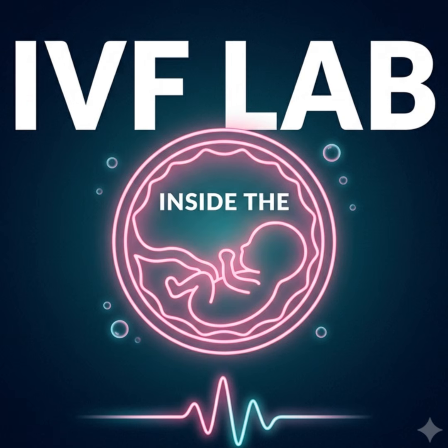Turning that coarse focus knob, absolutely terrified that you're going to drive that heavy metal lens straight down and crush the glass slide. Yes, because the focal length requires the glass to be practically touching the sample. And if you have a massive, bulky metal lens block sitting directly on top of the Petri dish containing your oocyte, the airspace is completely occupied. So where do your surgical tools go? How do you introduce a 5-micron needle into that environment? The clearance is 0. You have a visual field, but you've sacrificed all operational access.